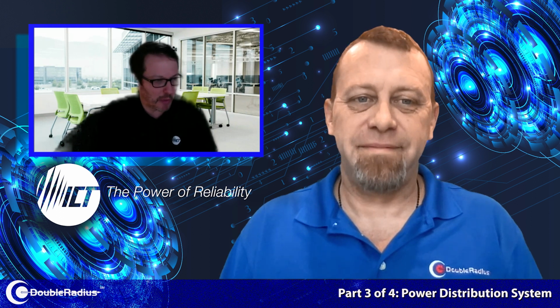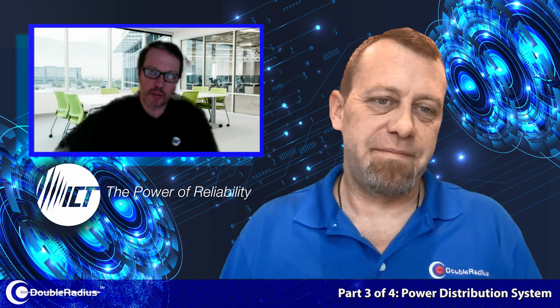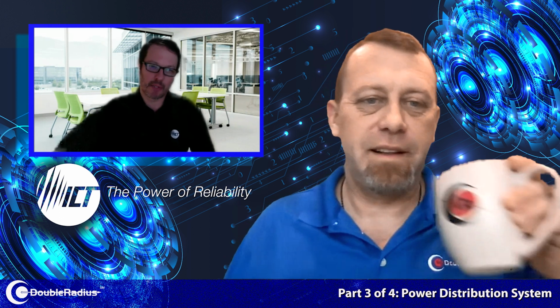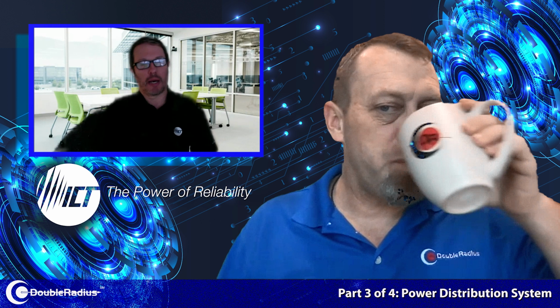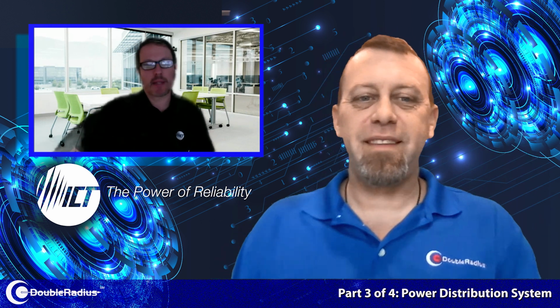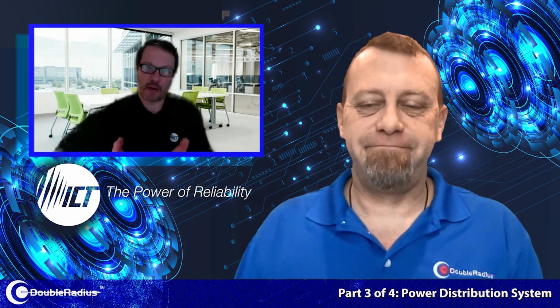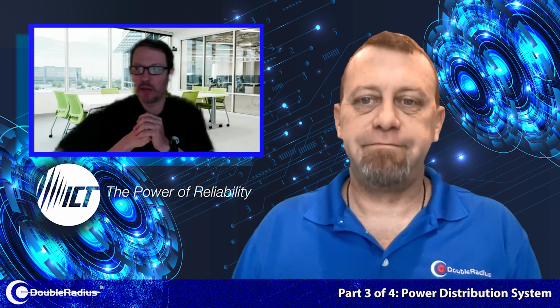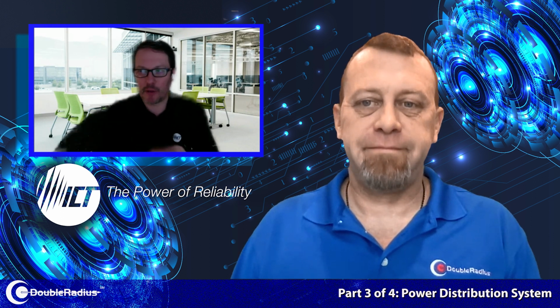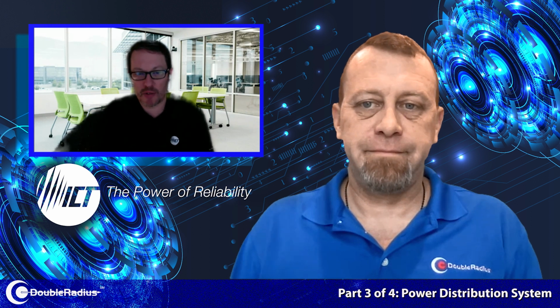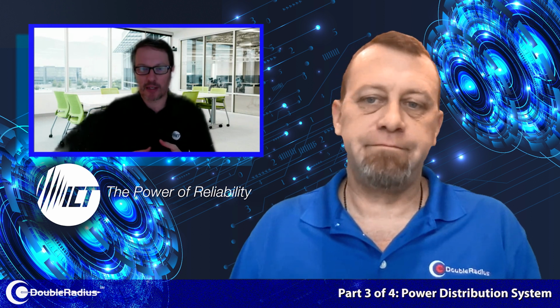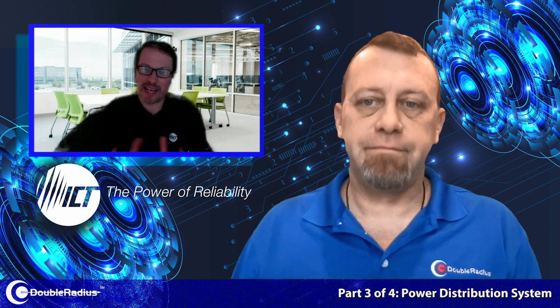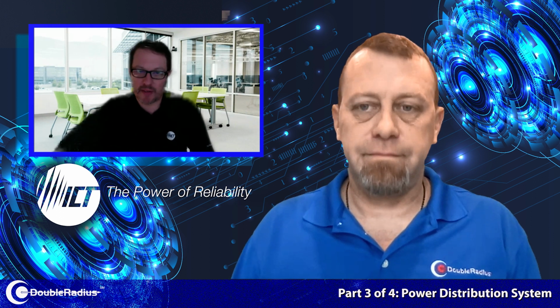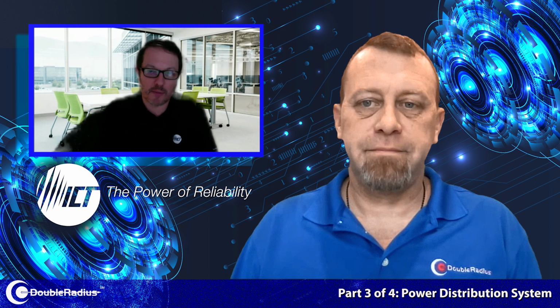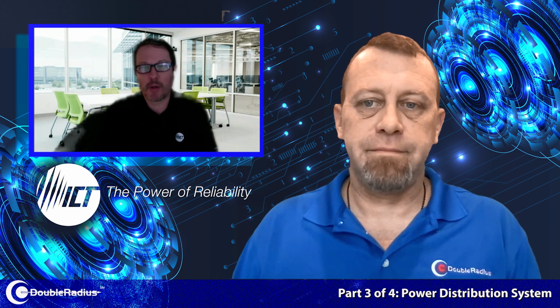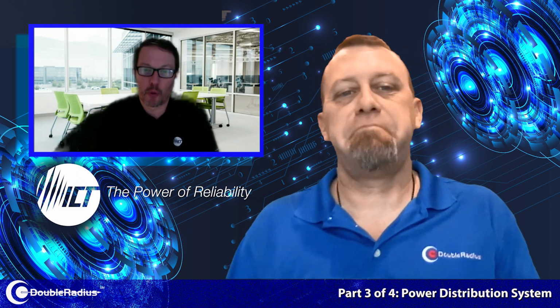And then lastly, I'd talk about the network watchdog feature, which is really important to a lot of customers. We're able to send pings out to the routers and switches that are in the local area network at the tower. So if your router locks up, and you can't communicate with the router, you've lost communications to your whole site. Well, our device can continue to ping that router because it's connected to it on the local area network within the site itself. If it doesn't get an answer from that router, it presumes that it's locked up. You can have it cycle power to that router and reboot it automatically.